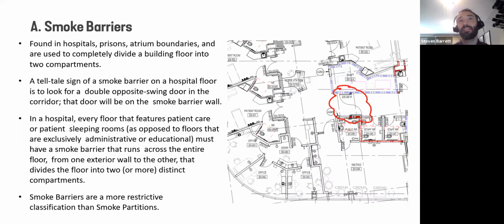The reason hospitals are designed like this is because you can't evacuate patients that are in beds. You can't tell them to go run down the stairs. So the strategy in hospitals is defend in place. So it's more of a relocation than an evacuation. So what happens is if you have your floor plan split in two, take the patients on side A, where the fire was, and move them into side B. So that's why the floor plans are split, at least in half, often into multiple smoke compartments for patient evacuation. And a smoke barrier, just like with fire barriers, is more restrictive than the smoke partition, in the same way that fire barrier is more restrictive than fire partition.